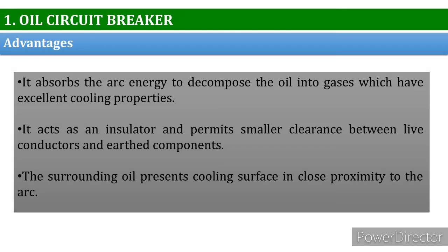There are advantages and disadvantages of this oil circuit breaker. If we talk about the advantages, it absorbs the arc energy to decompose the oil into gases, which have excellent cooling properties. The cooling is important. The faster the cooling is done, the quicker the arc is extinguished.